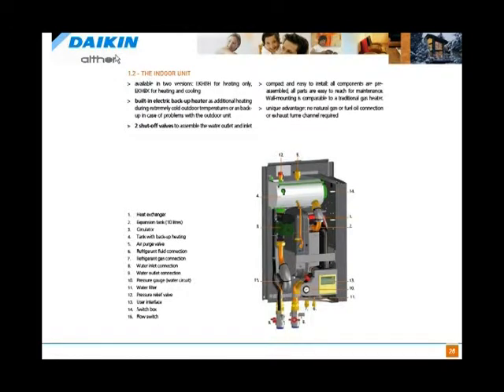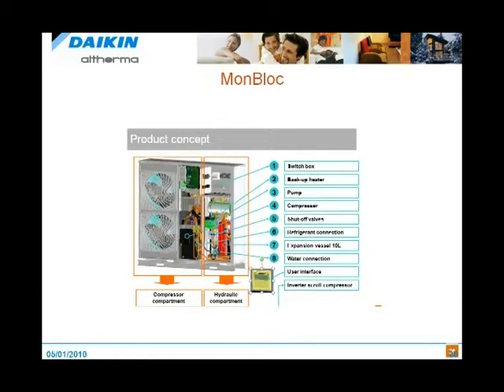Lines, 5/8 and 3/8 to the unit when it's indoor, and you have hot and cold, your hot supply, let's say supply and return lines coming out of the box. If you have a monoblock, you can see that the hydraulic component cabinet is on the right-hand side, and it has exactly the same components. You'll see that user interface, both if you have a hydrobox inside, or particularly if you have a monoblock, can be remotely located anywhere you want in the house.